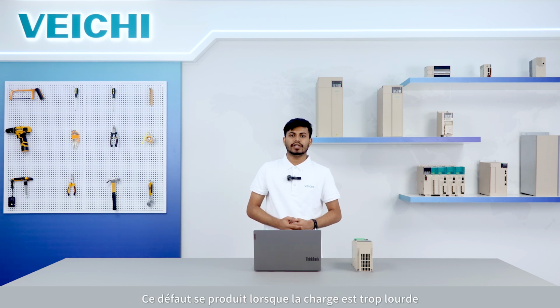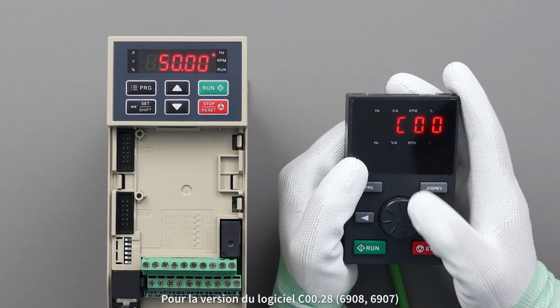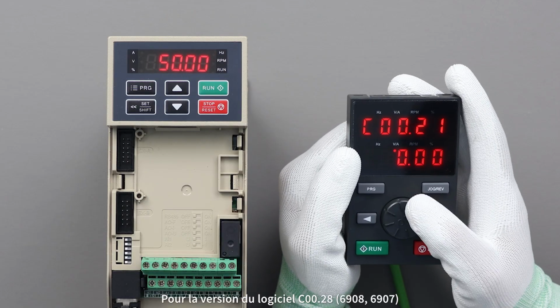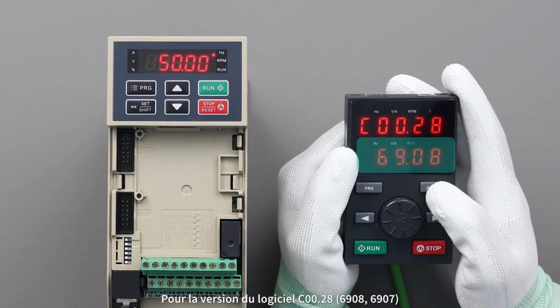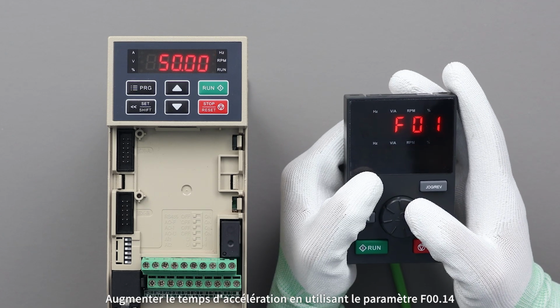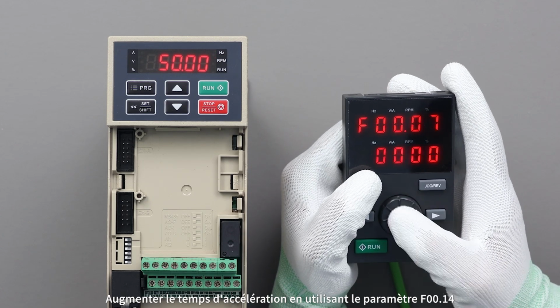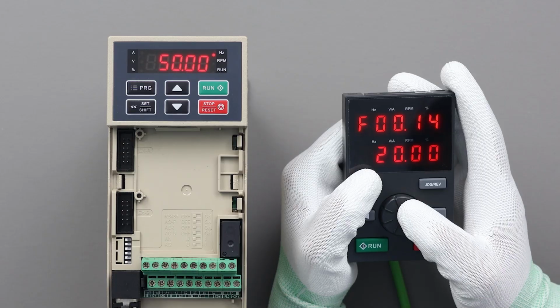First, identify the fault. This fault occurs when the load is too heavy and the acceleration time is too short. Adjust acceleration time. For software version C0028, 6908 and 6907, increase the acceleration time using parameter F00.14.